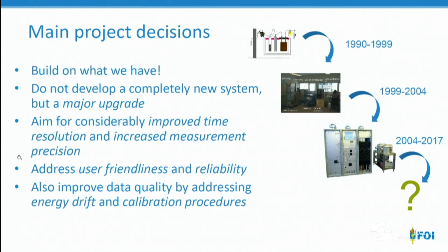We would like to aim for considerably improved time resolution and increased measurement precision, and also address the user friendliness and reliability. Another thing that's really important for us is to improve the data quality by addressing the energy drift and calibration procedures. We have had some drifts of the energy scale due to temperature, and we wanted to address that as well, and also improve the calibration.